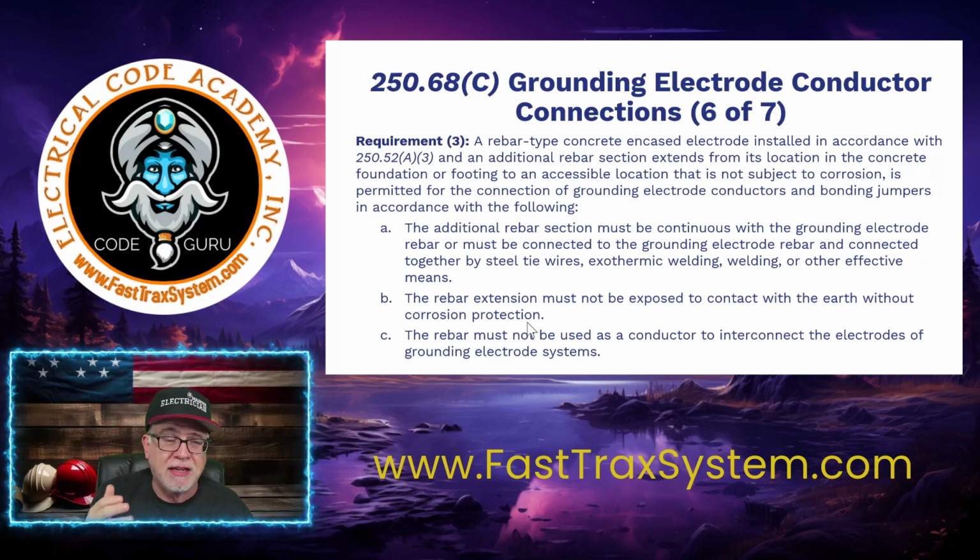I'll remind you, if this extends and it's exposed, then it still has to be accessible. But remember, a normal connection to the concrete encased electrode allows you to go down into the footing and make a connection, like a 4-gauge copper going down to the rebar, and those connections don't have to be accessible. We saw that earlier. But if you're going to use rebar and extend it up from the actual concrete encased electrode, then those connections are going to have to be accessible. And if it's exposed to or in contact with the earth, then you're going to have to put some corrosion protection over all of that connection. Easiest thing to do is don't do that. Bring it up into the wall.